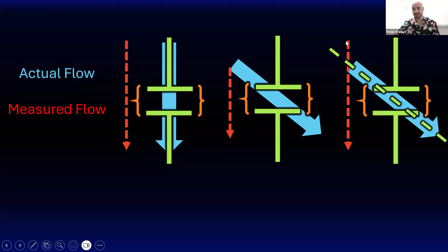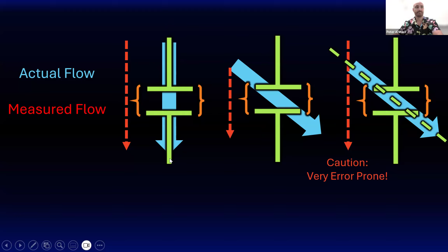The problem with this is it's very error prone. As you move that angle more and more perpendicular to the flow, the machine's kind of guessing what the flow is. You're picking up signal and noise rather than true flow. So you really want to get the gate in line with the flow as much as possible. Get it in line with the flow as much as you can.